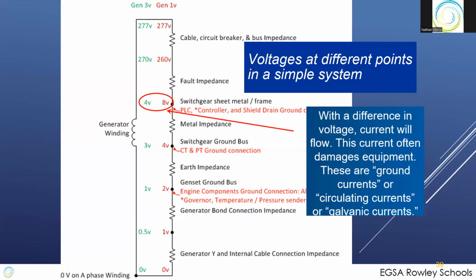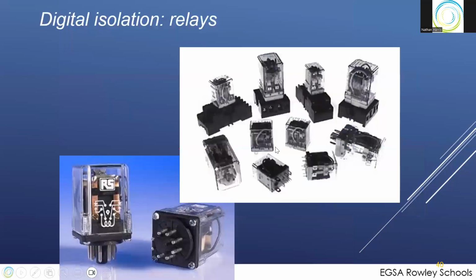So we need to specify galvanic isolation on our load share lines, our bar share lines, all these analog signals. Digital's not as much of a problem anymore. The new digital controllers, whether using CAN bus or others, it's not a problem. It's a differential signal. You don't connect the grounds. You don't worry about it. But in analog systems, you definitely have to be very conscious that that's a galvanically isolated signal.